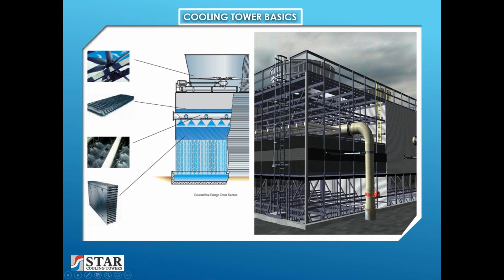The counterflow cooling tower is quite different. The hot water comes into an individual header in each individual cell and has a series of distribution laterals coming out either side that incorporate low pressure distribution nozzles. As you can see, the film packing is cubes of PVC, and they can be different depths determined by the cooling requirements of the cooling tower. Again, drift eliminators are installed horizontally above the header system to remove the water droplets before it goes to the fan. And again, the mechanical equipment, rotating equipment, is identical to that of the cross-flow cooling tower.